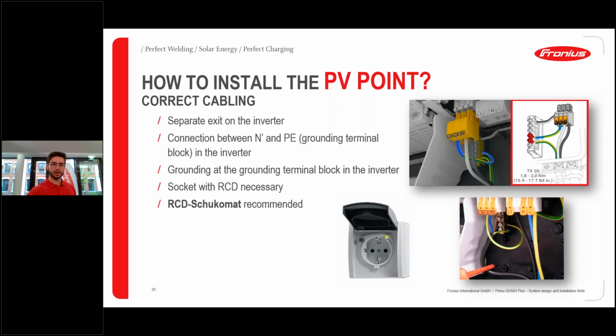Yeah, we can also see down below an RCD integrated socket. So this is also what we can recommend, but of course you can do 2 separate components as well. Of course, it's possibly a price question here, what to choose, but both of them are working fine. And for the RCD itself, a type A RCD is sufficient. 30 milliamps, our type A RCD is the way that we need to secure this line.